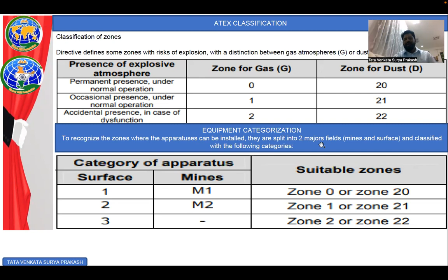Now let's quickly look at minimum source of ignition energy for gas groups. Four groups of gases are defined based on the characteristics of representative gases, used for the type test, for example equipment type or apparatus group. Group 1 is for mines, called gas group 1, where methane is present, and the minimum ignition energy for methane is 300 micro-joules. Group 2 is for surface applications, for example 2A, 2B, and 2C.